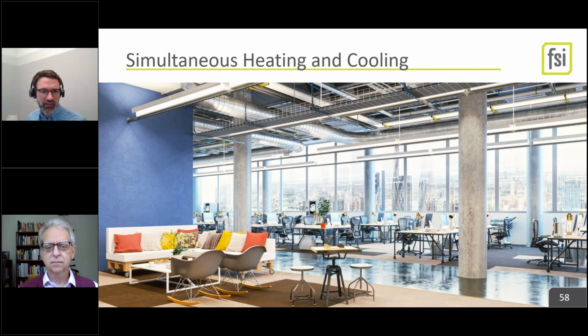So there are ways to handle that which allow you to not deal with this, but dealing with it, it's primarily a controls and commissioning issue. And our commissioning group really hates it when this happens, because you have to not only check that this thermostat does its temperature change and does what it's supposed to do at its zone, but that the other one that's linked to it, that's an internal zone, also goes up and down with it. So it's an easy thing to miss in commissioning. It's a bit of a pain to program for the controls folks.